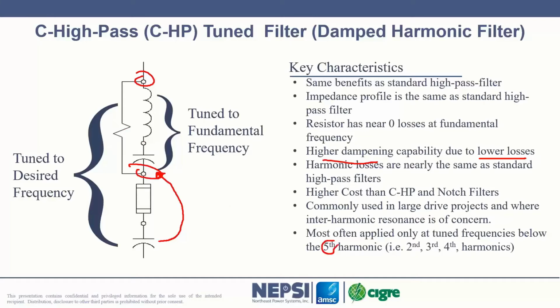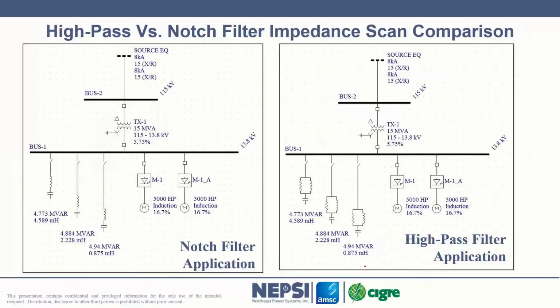Typically, you don't ever see above a frequency of the fifth harmonic. Okay, that's in my experience, the fifth harmonic is where we stop with the C high pass filter. Okay, at a seventh, it tends to be difficult even to find components to properly do it.